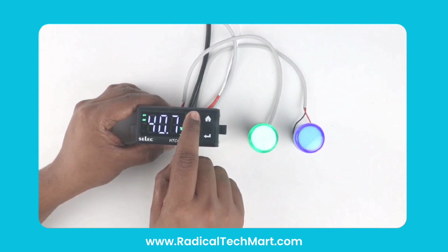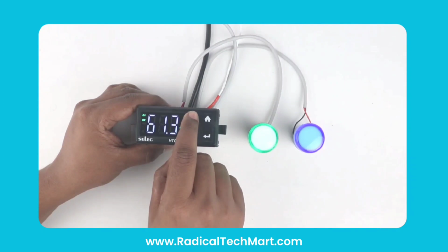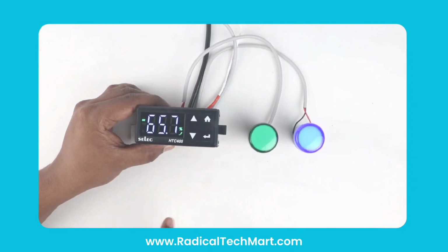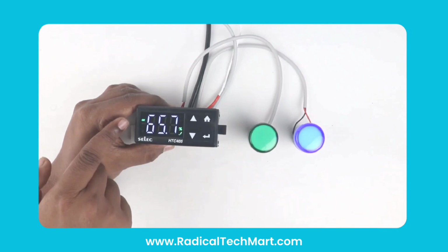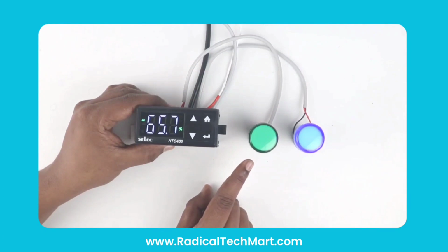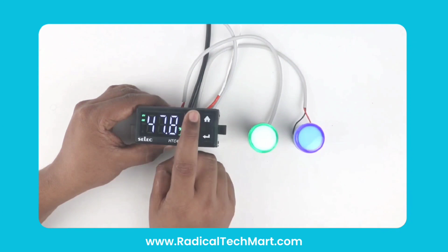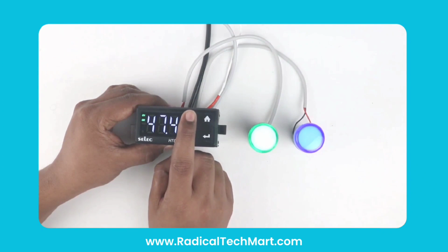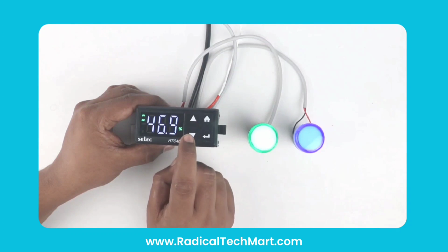For example, I will change the humidity set point. When I set it to 65, the output turns off because the actual humidity is 61.7, which is below the set point. If I lower the set point to 40, the relay turns on, and the green LED lights up.